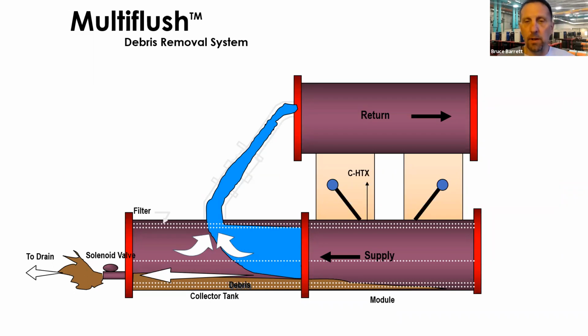There's a lot of concern out there for braze plate heat exchangers and debris on open systems getting into your heat exchangers. One thing we have done is added an inline strainer to the entering water connections on both the condenser and the evaporator side to keep that debris from getting into the heat exchanger. Now, we still require an external strainer. You want to capture it before it gets into the chiller. But just another added line of defense.